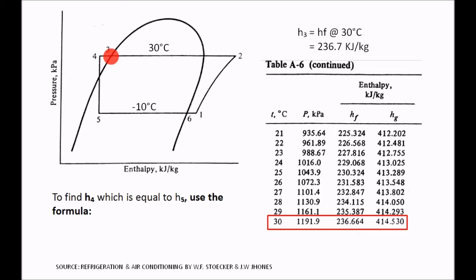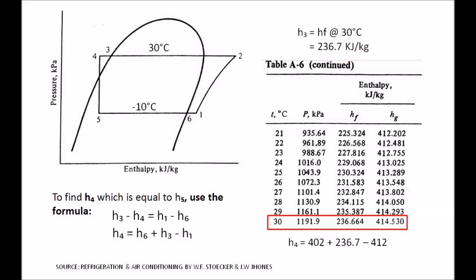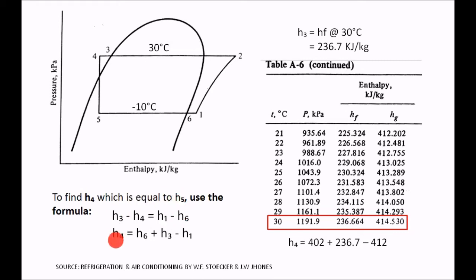To find H4, which equals H5: using the heat balance equation H3 minus H4 equals H1 minus H6, we derived earlier. Rearranging: H4 equals H6 plus H3 minus H1. Transferring terms: H4 is on one side, H1 and H6 on the other. So H3 from the table at 30 degrees Celsius is 236.7 kJ/kg — that is 236.664 rounded to one decimal place.